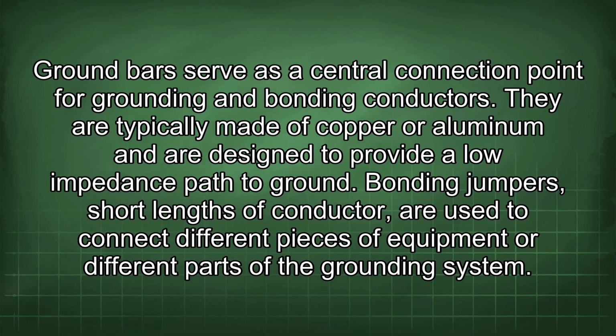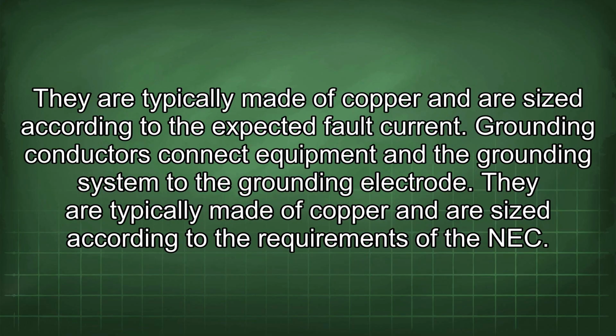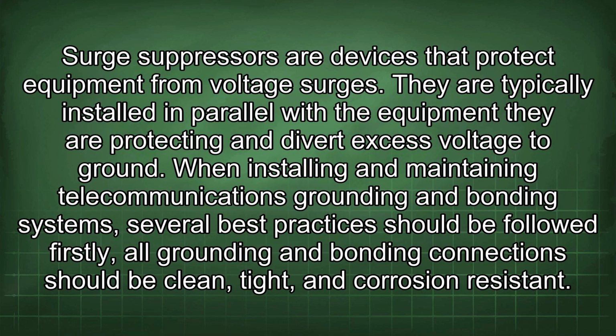Bonding jumpers, short lengths of conductor, are used to connect different pieces of equipment or different parts of the grounding system. They are typically made of copper and are sized according to the expected fault current. Grounding conductors connect equipment and the grounding system to the grounding electrode. They are typically made of copper and are sized according to the requirements of the NEC. Surge suppressors are devices that protect equipment from voltage surges. They are typically installed in parallel with the equipment they are protecting and divert excess voltage to ground.